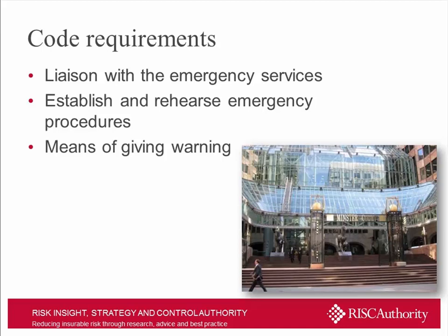And again, what you're going to use in each one of the different environments and different scenarios is going to differ, from a klaxon or a handbell to a fairly comprehensive fire detection and alarm system, should that prove to be necessary due to the nature of the premises. Some sites may require a hardwired and linked system with call points, and others may use wireless type systems, which enables a degree of greater flexibility in maintaining effective systems across the site.